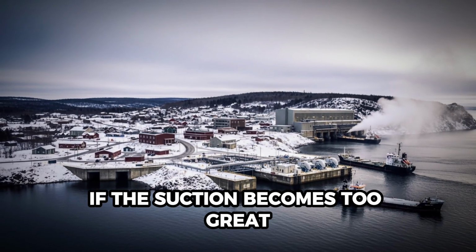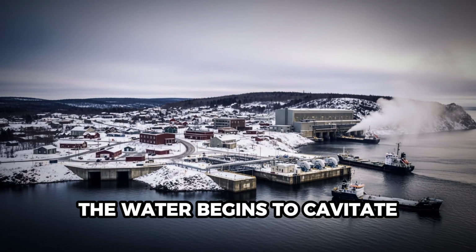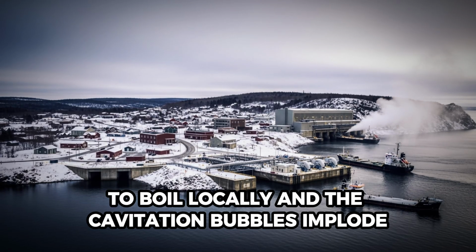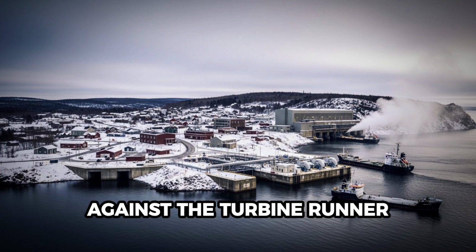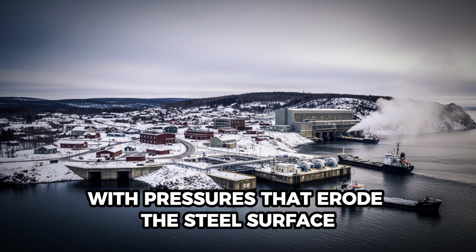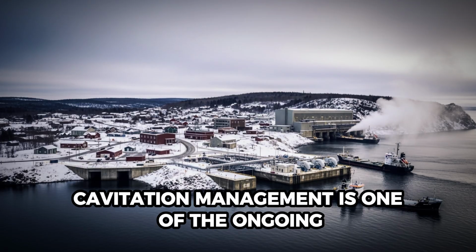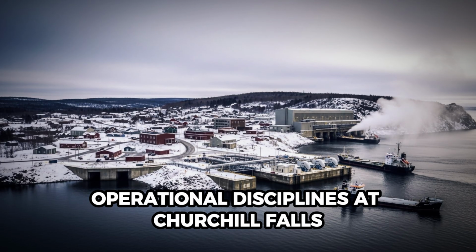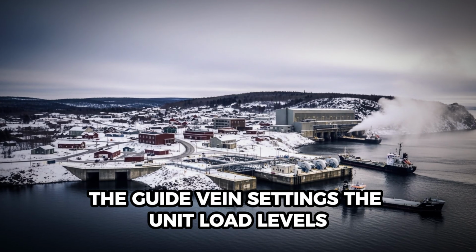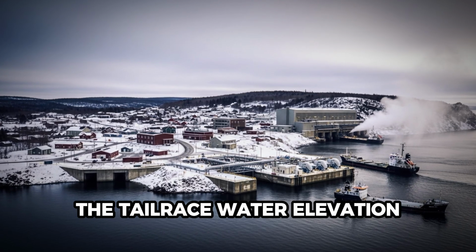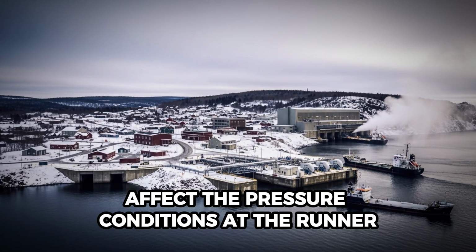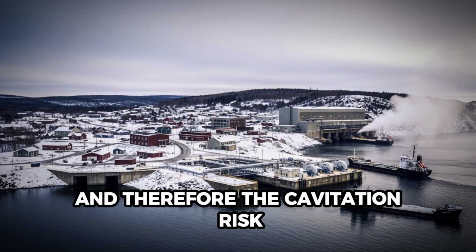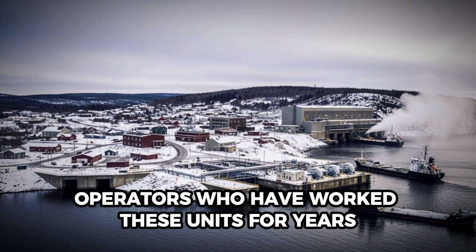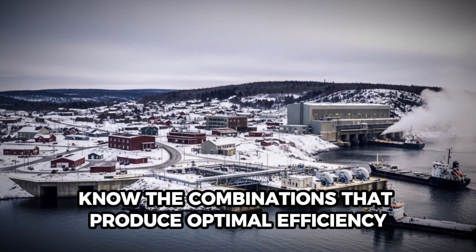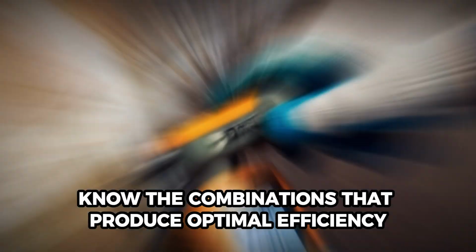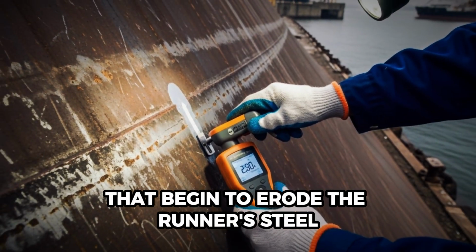If the suction becomes too great, the water begins to cavitate, to boil locally, and the cavitation bubbles implode against the turbine runner with pressures that erode the steel surface. Cavitation management is one of the ongoing operational disciplines at Churchill Falls. The guide vane settings, the unit load levels, the tail race water elevation, all of these affect the pressure conditions at the runner and therefore the cavitation risk. Operators who have worked these units for years know the combinations that produce optimal efficiency and the combinations that begin to erode the runner's steel.